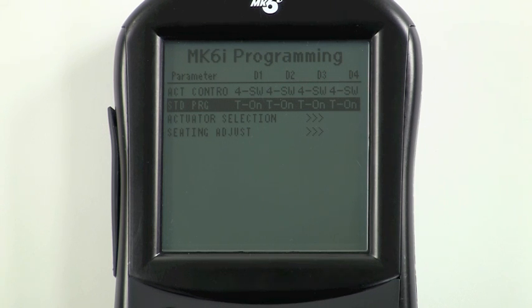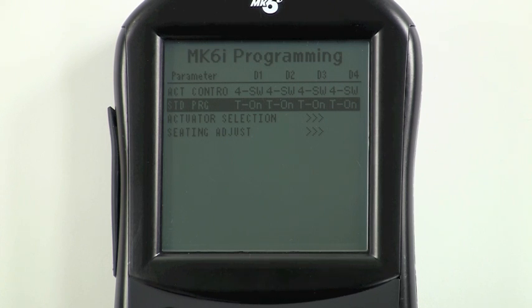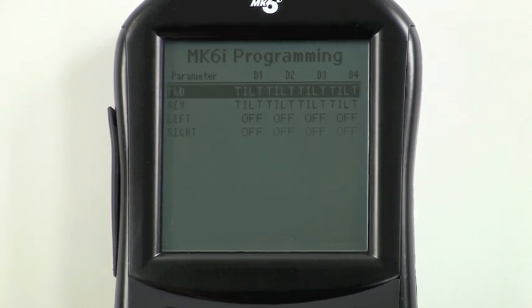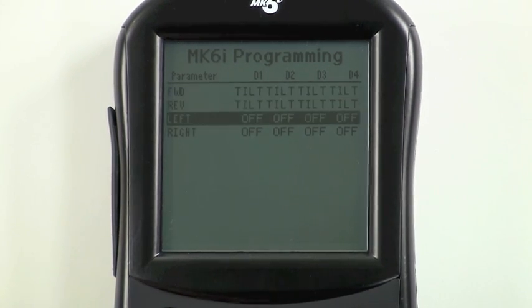If you want to customize quadrant assignments, scroll down to the next menu choice, actuator select, and press select. Scroll to the desired quadrant — in this case we're going to choose left. We're going to highlight all drives, as we're setting up powered seating in all drives.